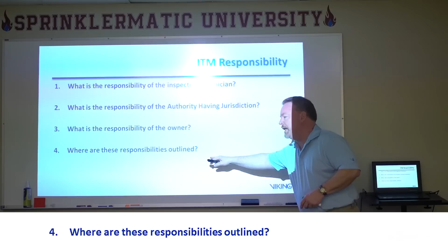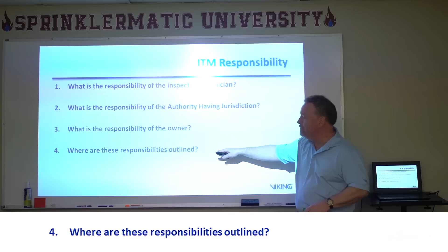So we kind of went all the way around where they outlined all of these responsibilities. The responsibility of the owner is detailed in NFPA 25. The responsibility of the inspection technician is detailed in the contract with the owner. They have to know NFPA 25, but they can't apply NFPA 25 until they're under contract with the owner to do so. So they need to know the contract, and the inspection technician needs to know NFPA 25, they need to be qualified to do that.